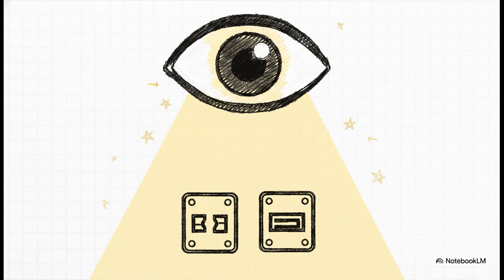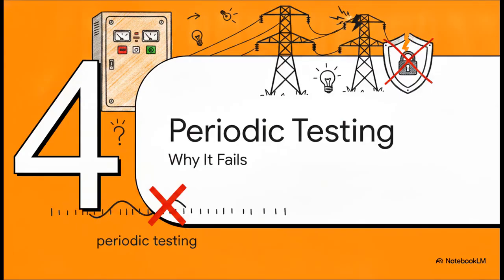If a wire happens to break while the breaker is open, you'd have absolutely no idea until you close it again and then, tragically, try to trip it during a fault. Continuous dual-state monitoring completely eliminates that risk. Section 4. Why periodic testing fails.